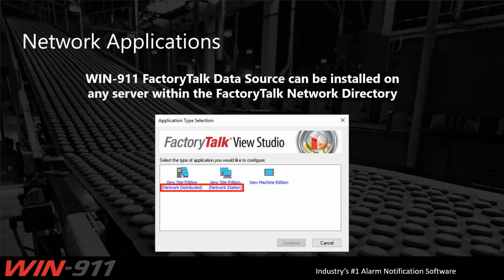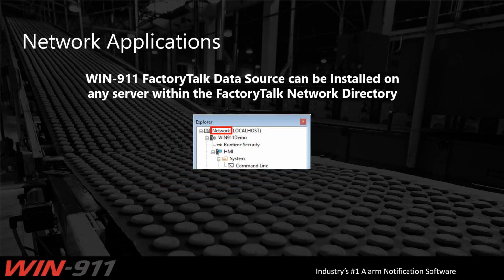If you are running a network application, you can install the WIN-911 data source on any server within your FactoryTalk directory. It doesn't have to be on the same server as FactoryTalk. It can be on any standalone server. However, you're going to have to have it join up to your FactoryTalk directory. Same thing, if you're not sure if your application is network or not, it's pretty obvious: when you open up an application, it will say so here, or in your Explorer pane, it will say network at the top.